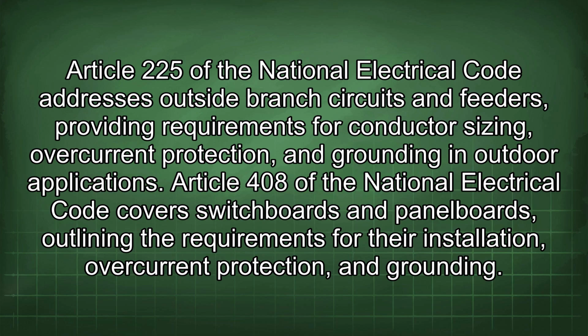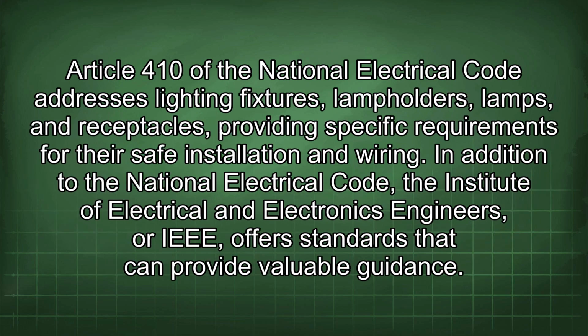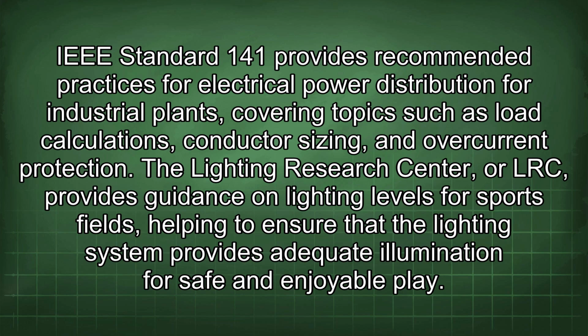Article 408 of the National Electrical Code covers switchboards and panel boards, outlining the requirements for their installation, overcurrent protection, and grounding. Article 410 of the National Electrical Code addresses lighting fixtures, lamp holders, lamps, and receptacles, providing specific requirements for their safe installation and wiring. In addition to the National Electrical Code, the Institute of Electrical and Electronics Engineers, or IEEE, offers standards that can provide valuable guidance. IEEE Standard 141 provides recommended practices for electrical power distribution for industrial plants, covering topics such as load calculations, conductor sizing, and overcurrent protection.